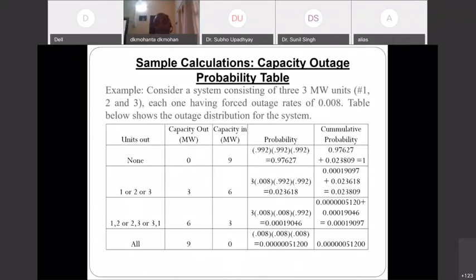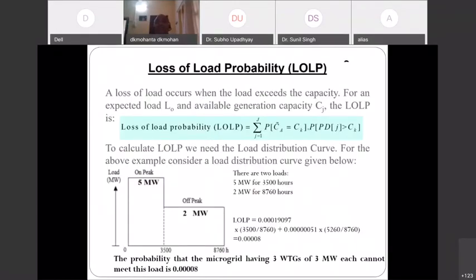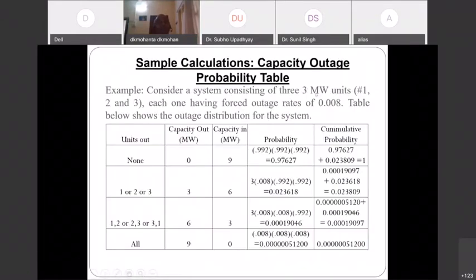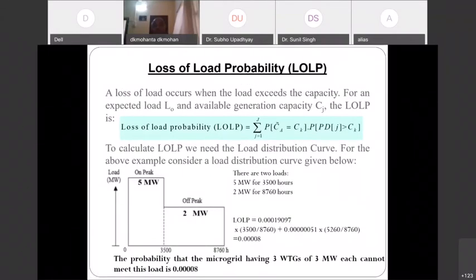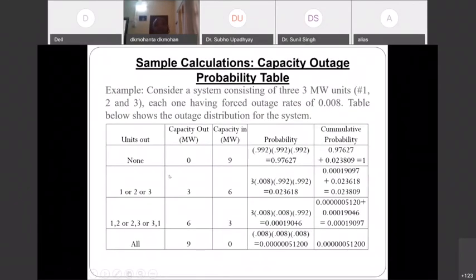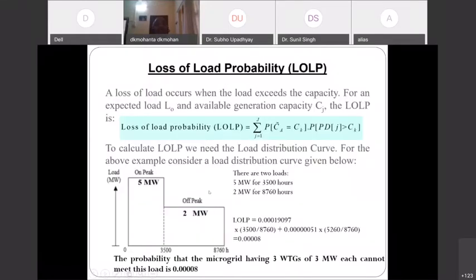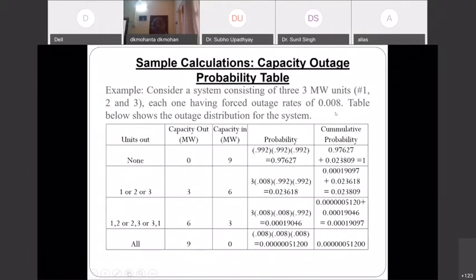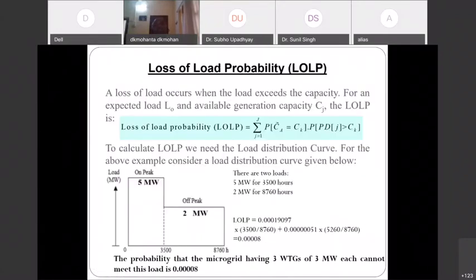Now, what is loss of load probability? I'll explain here. Here, we have 3 units, each of 3 megawatt. So my generation capacity is 9 megawatt. And I have deliberately taken a load such that on peak it is 5 megawatt, and off peak it is 2 megawatt. So definitely my generation is 3 megawatt times 3 units, 9 megawatt. But my load is sometimes on peak 5 megawatt, and when not peak it is 2 megawatt. So it seems that it is a very reliable system. But you will see that still there will be loss of load probability.